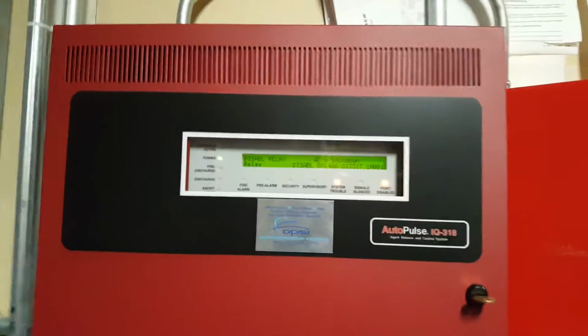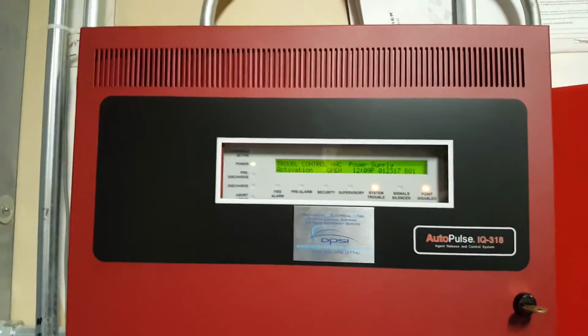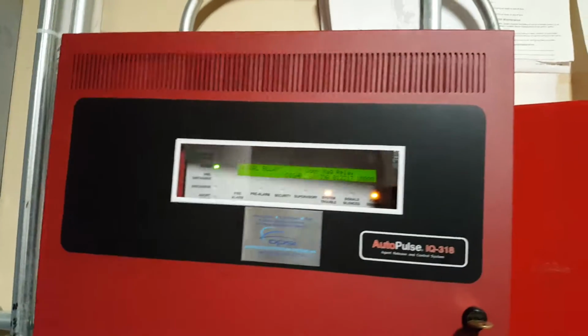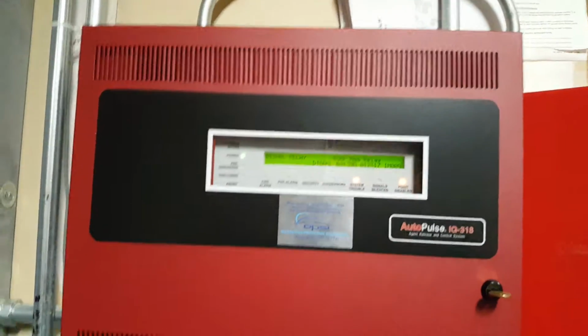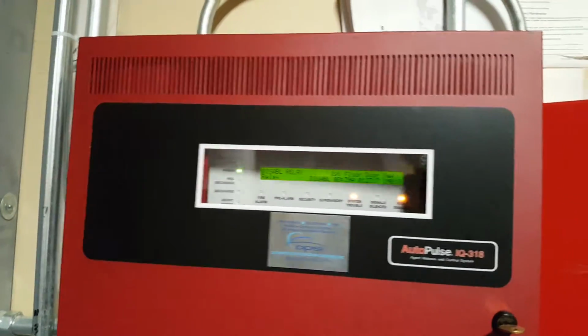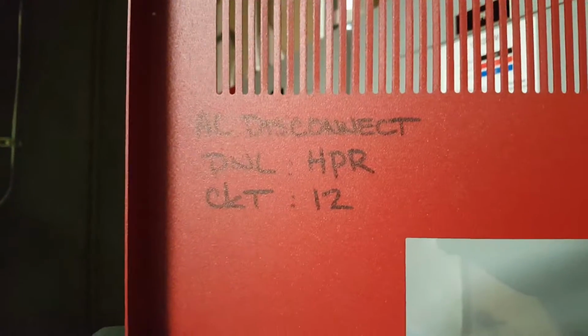In this video, I'm going to show you how to do an AC disconnect test on your fire panel. Typically on the exterior of the panel or somewhere listed will be the AC breaker panel and the disconnect. On this panel, it's on the inside. So they have written AC disconnect panel HPR, circuit 12.